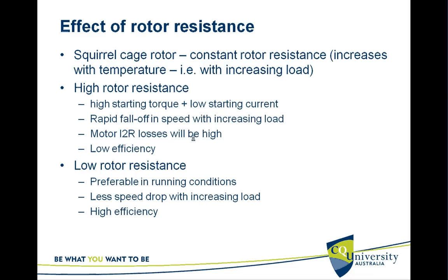Efficiency will therefore be low with high rotor resistance. Low rotor resistance is preferable for running conditions — the speed drop will be less with increasing load, the motor can maintain pretty much the same speed, and efficiency will be high due to lower I²R losses.